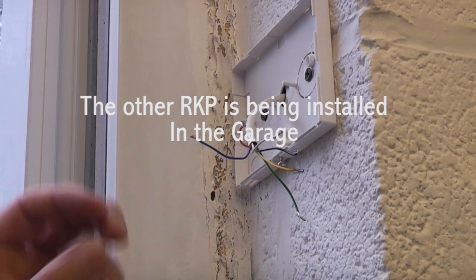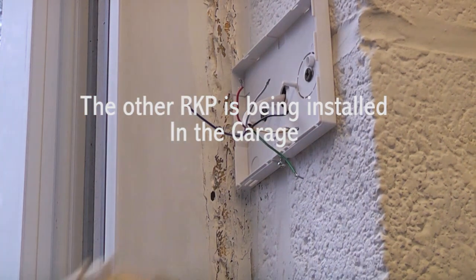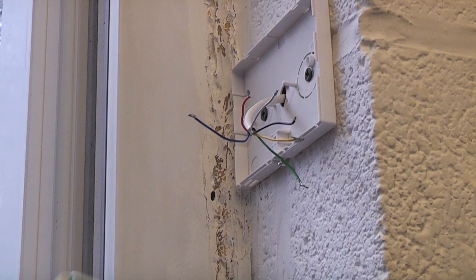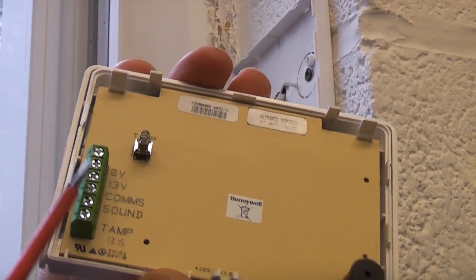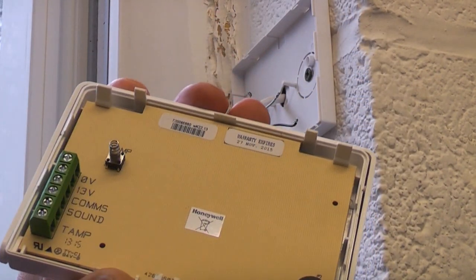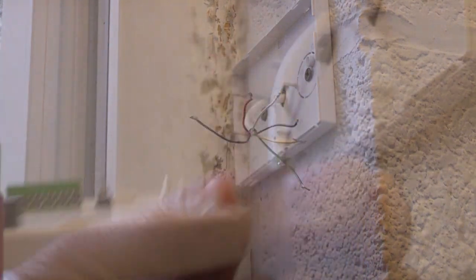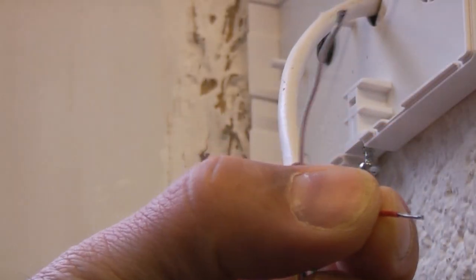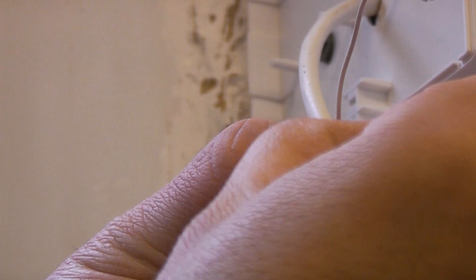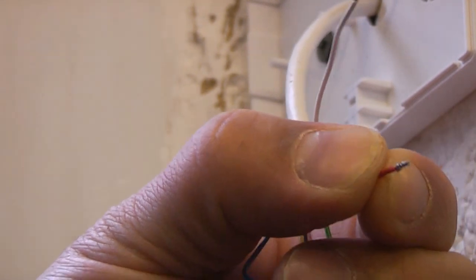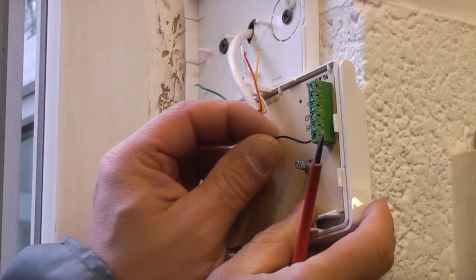We're now going to wire all of these wires into the back of the control panel. It's a good idea when you do this to write down which colored wire you have put where, because you need to repeat that in the actual alarm panel itself. I've now stripped 10mm from the end of every wire. I'm now going to twist all the strands together and then fold each conductor back on itself slightly. That will give us a really good connection inside of the remote.